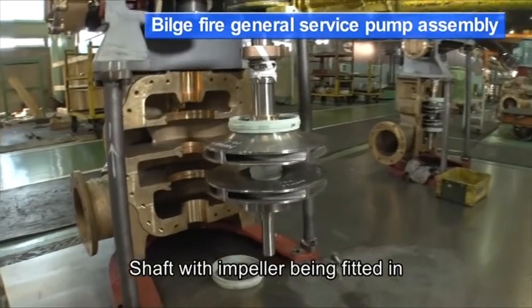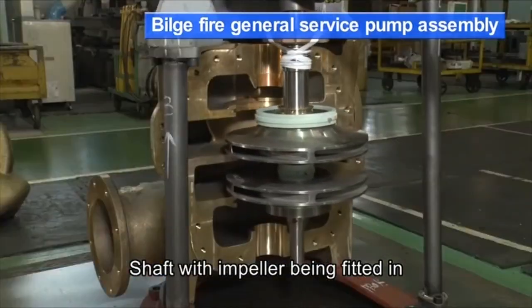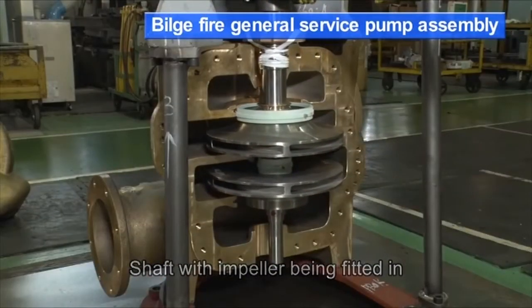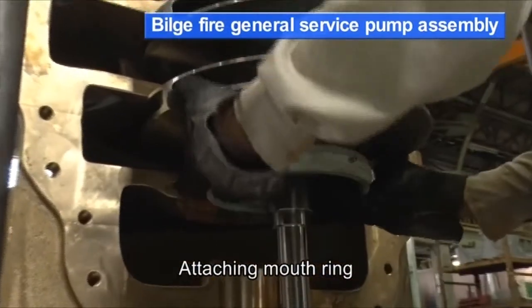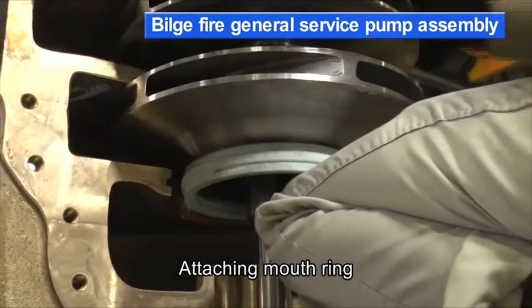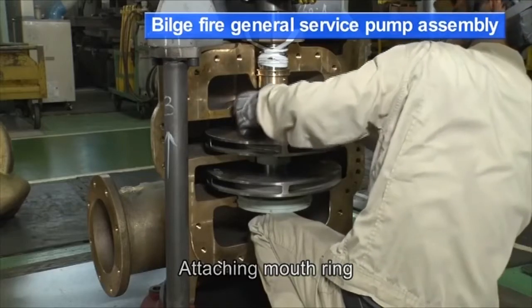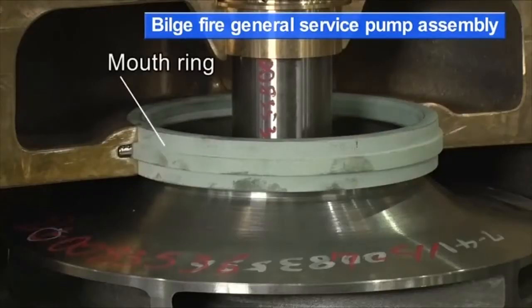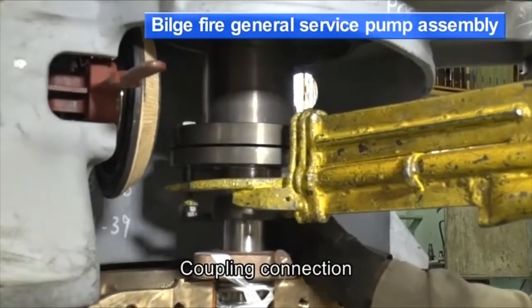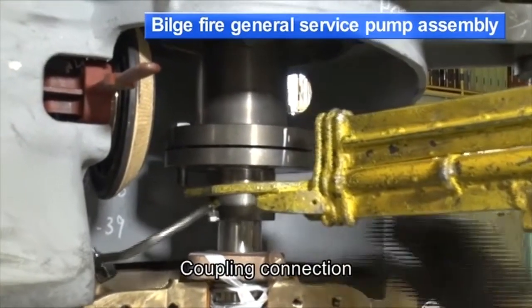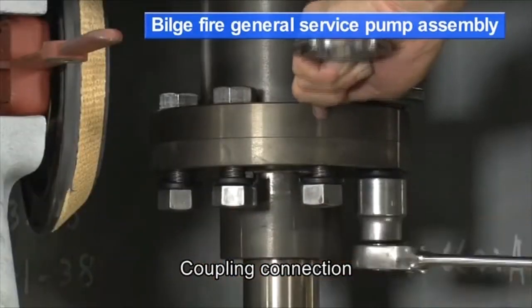The shaft with an impeller is fitted in. The mouth ring is attached. The coupling is connected. With pumps that have no line bearing at the bottom, alignment is fixed by motor coupling connection.